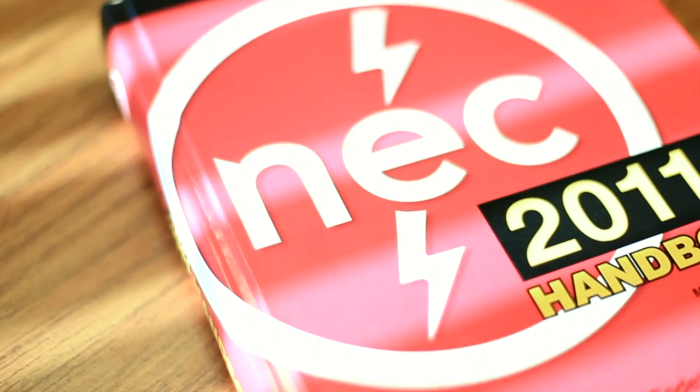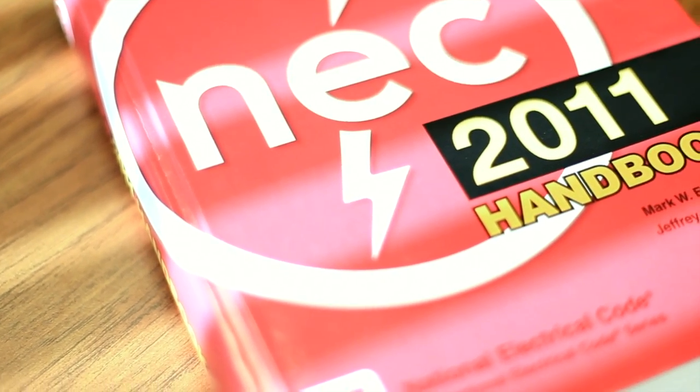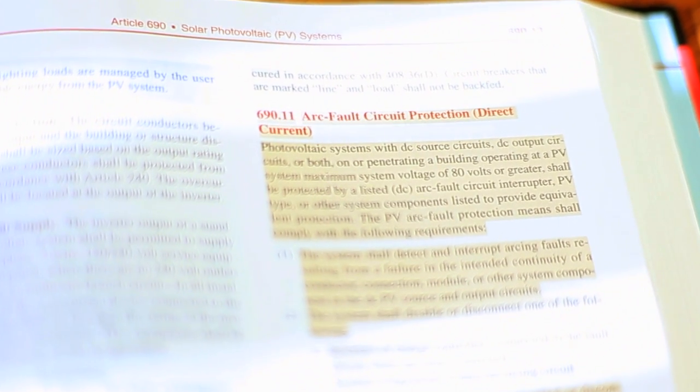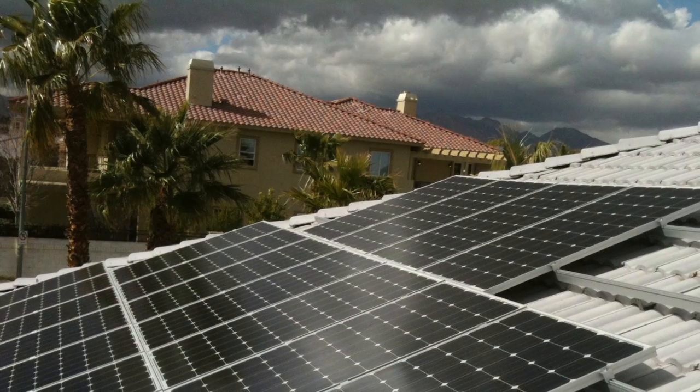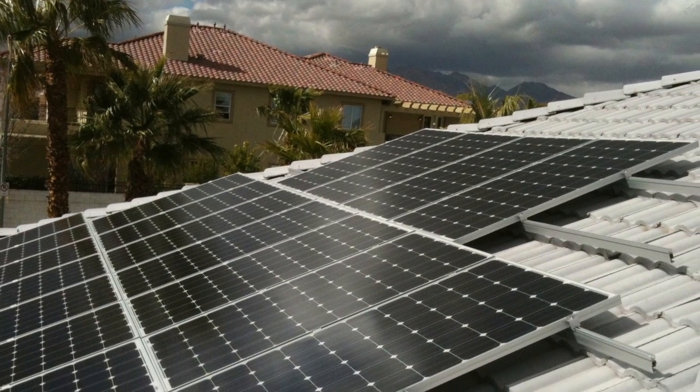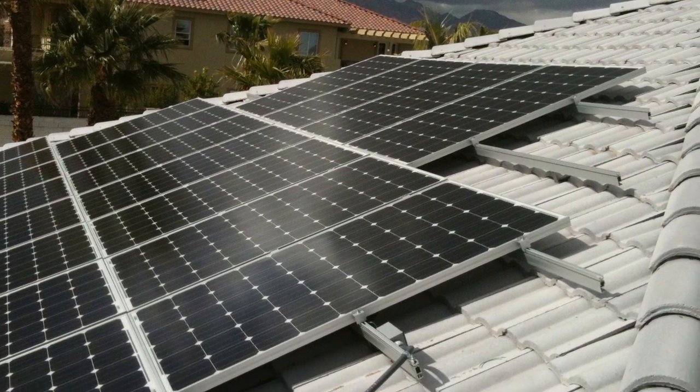The 2011 edition of the National Electrical Code requires DC photovoltaic installations to be protected by a DC arc fault device. This requirement mitigates arcing on the DC side, significantly reducing the risk of fire.